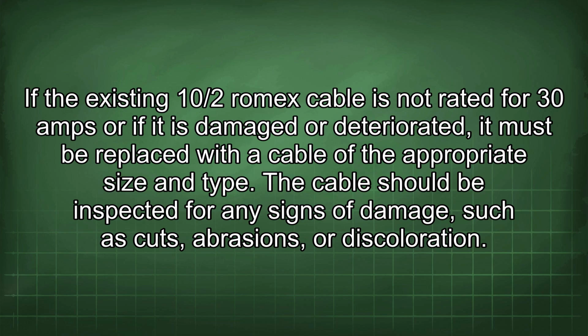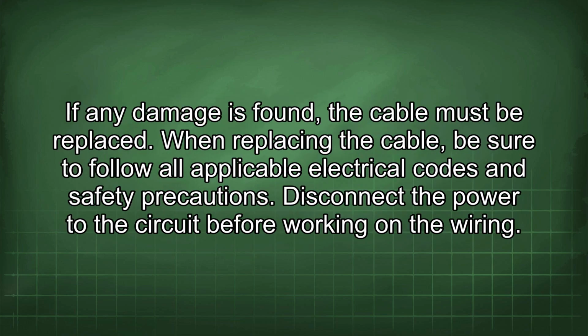If the existing 10/2 Romex cable is not rated for 30 amps or if it is damaged or deteriorated, it must be replaced with a cable of the appropriate size and type. The cable should be inspected for any signs of damage such as cuts, abrasions, or discoloration. If any damage is found, the cable must be replaced. When replacing the cable, be sure to follow all applicable electrical codes and safety precautions.